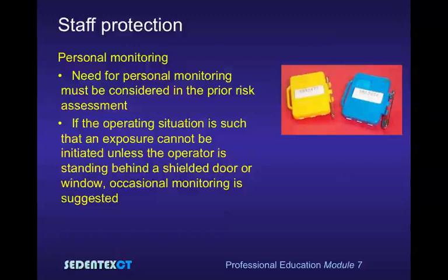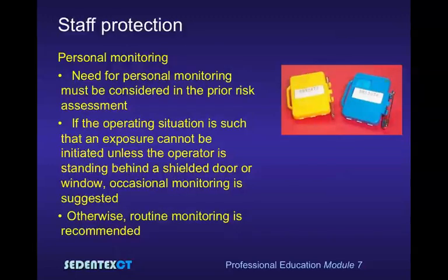But in situations where personal monitoring is not mandatory, if the operating situation is such that an exposure cannot be initiated unless the operator is standing behind a shielded door or window, then in that case only occasional monitoring is suggested. In any other situation, for cone beam CT, routine monitoring is recommended.